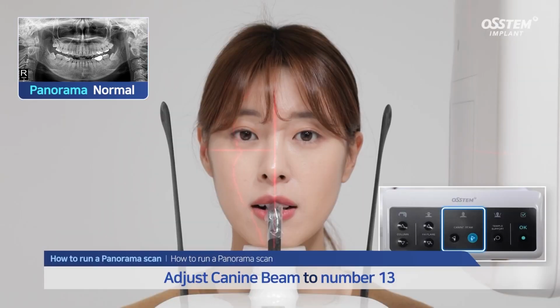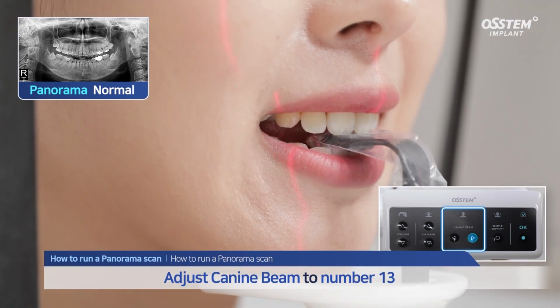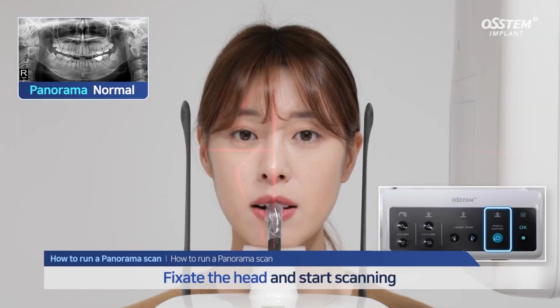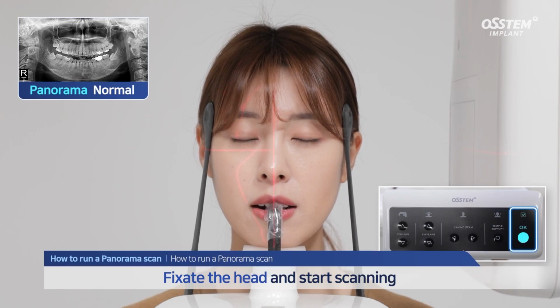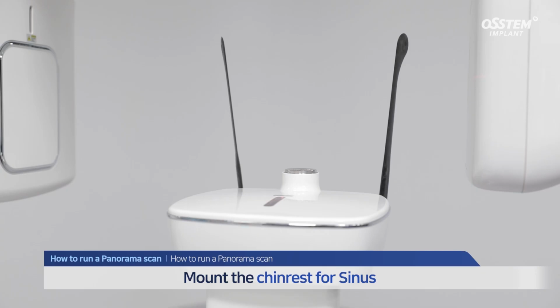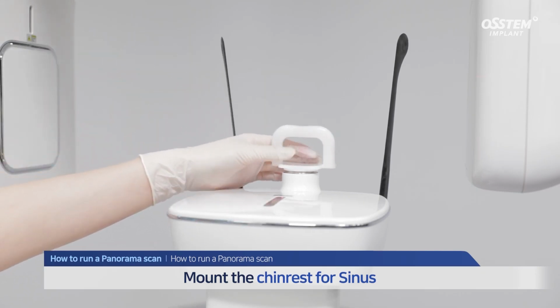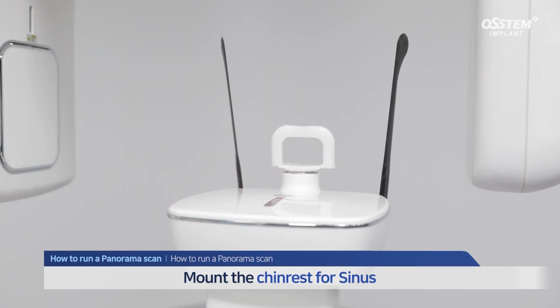Place canine beam on the number 13 teeth. Press the temple support button to fixate the patient's head and then press the OK button to start scanning. Replace the chin rest with the one used only for sinus scans.